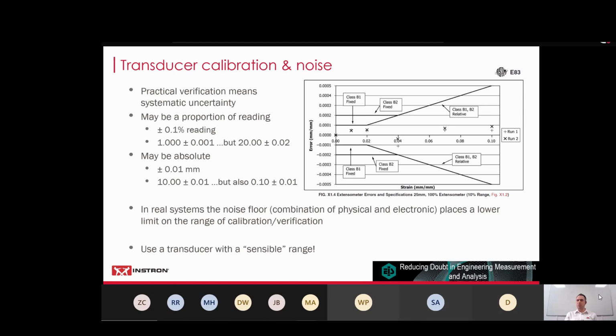And this prompts me to say, when you're doing measurements, please use a transducer with a sensible range. If you're going to have a specimen where you're going to apply a force of, let's say, 500 newtons, and that's the biggest force you're going to apply, please don't do this using a load cell which is rated for 100 kilonewtons, because you are way down, and while it will give you a measurement, and in fact, blowing our own trumpet here as Instron, we can sometimes control quite well, even despite a lot of noise on the signal, that doesn't mean it's a good idea or a good test. So you're looking to be using a reasonable mid-range of your transducer, not right stretching it to its absolute capacity, not right down near 0. You will get poor data, relatively speaking, out of that. And the proportional uncertainty becomes much, much bigger.